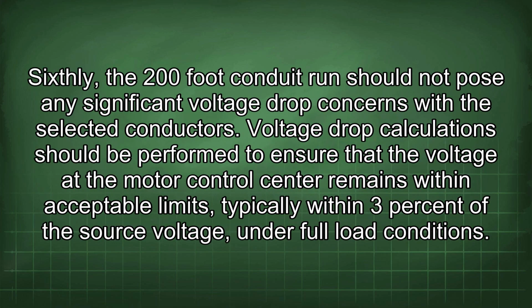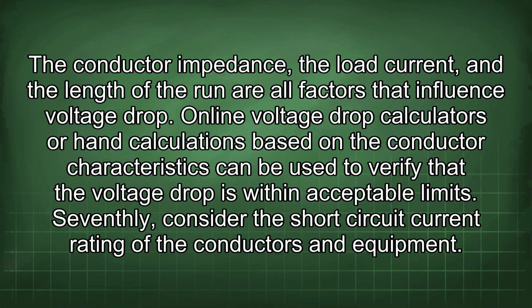Sixthly, the 200-foot conduit run should not pose any significant voltage drop concerns with the selected conductors. Voltage drop calculations should be performed to ensure that the voltage at the motor control center remains within acceptable limits, typically within 3% of the source voltage under full load conditions. The conductor impedance, the load current, and the length of the run are all factors that influence voltage drop.